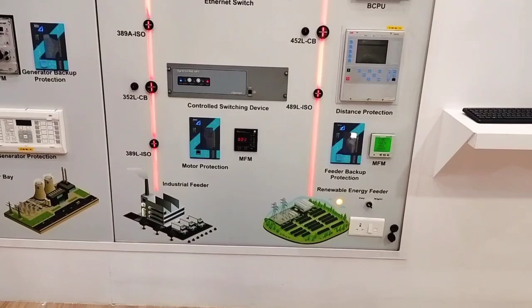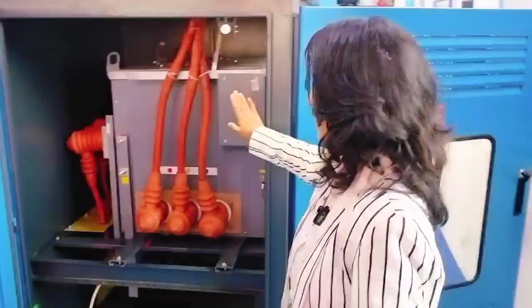This is a typical dry type transformer. We call this a VPI, vacuum pressure impregnated transformer. This is used for monitoring temperature, etc. It will run the fan, and show high or very high temperature according to the setting. It will accordingly give the primary side command. We use the primary side breaker.